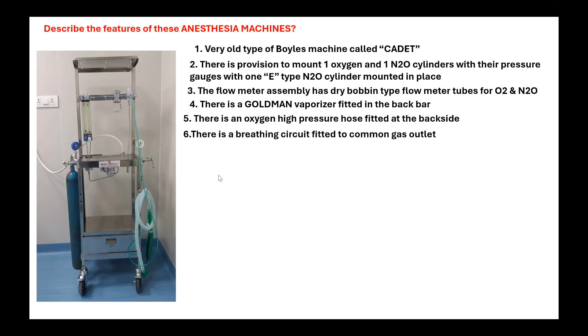Okay? So this was the oldest machine, Boyle's machine. After the prototype I showed you, which is very primitive, this was the improved version. Then, because they found that having one cylinder is risky, because halfway through, if the cylinder becomes empty, you have to deliver the gases with hypoxia because oxygen will not be available and you have to replace that. So they introduced provision for two cylinders in the later machine.